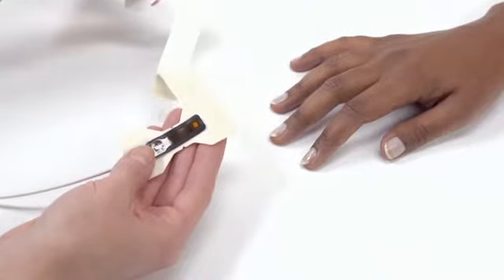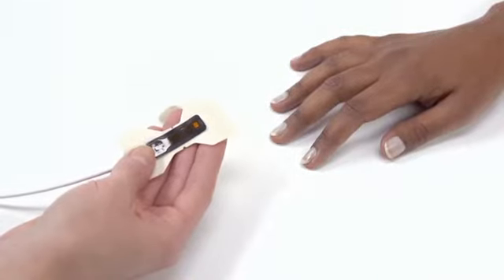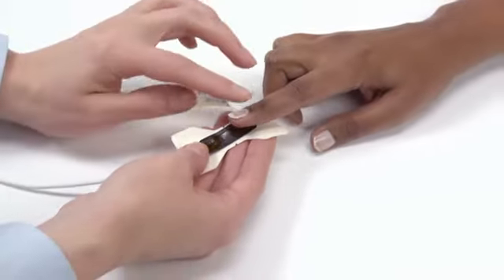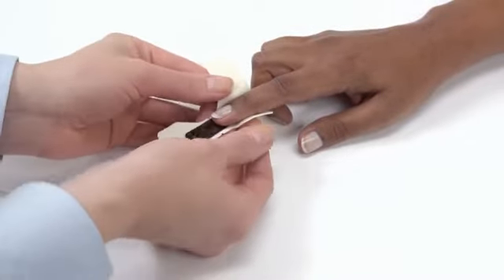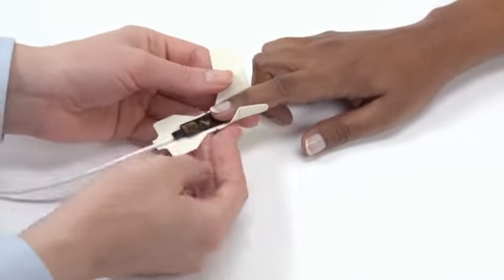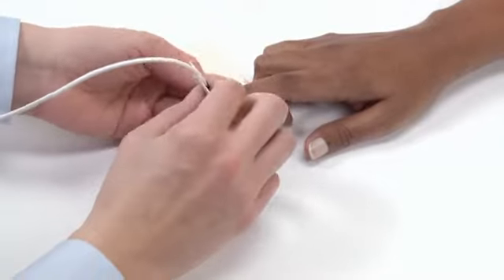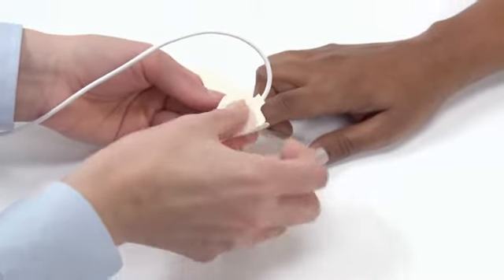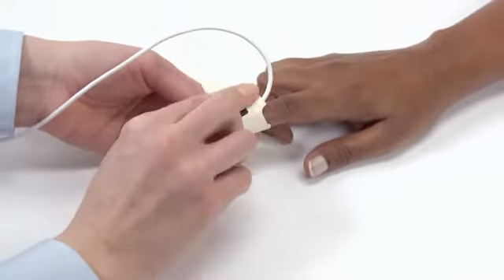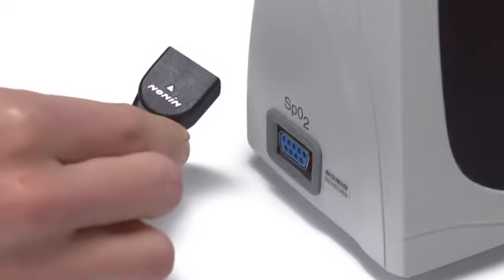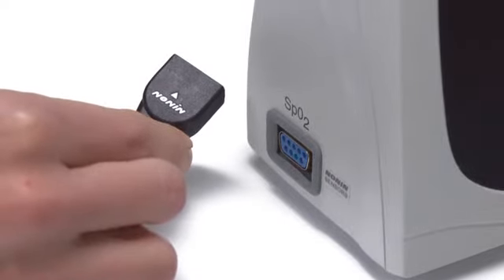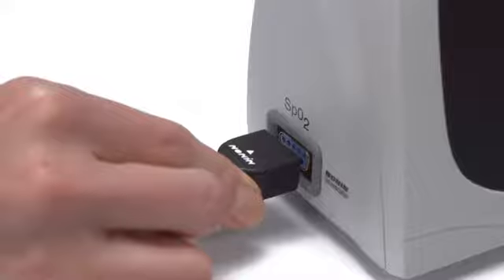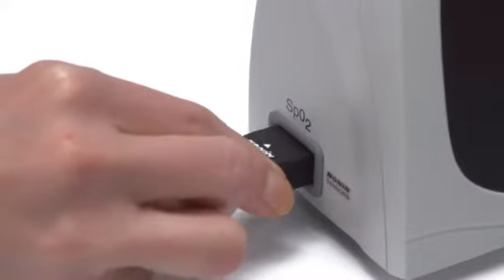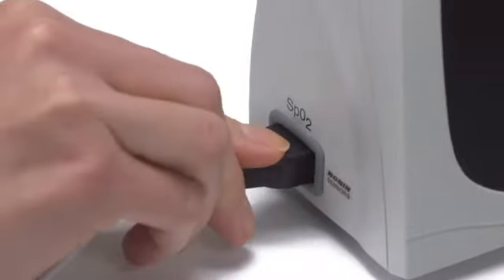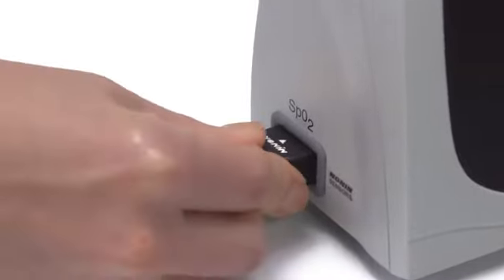Prepare and place the sensor on the patient prior to connecting it to the oximeter. Proper sensor placement is critical for accurate readings. Follow the instructions for each sensor type to ensure secure, aligned positioning of the sensor on the finger or skin surface. Connect the sensor to the pulse oximeter by inserting the plug, with the Nonin logo visible from the front, into the left side of the unit. The connector should firmly seat in the connector port on the oximeter.